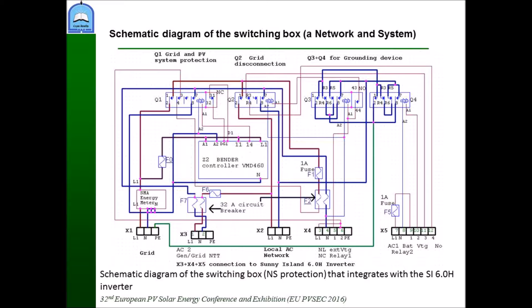It is controlled by a device monitoring voltage and frequency, called a Bender controller, which we've got in the switching box. It is the model VMD460. This is what we have in my system, and it works as a perfect system when I test the power quality and the response of the AC mini-grid system when the load changes.